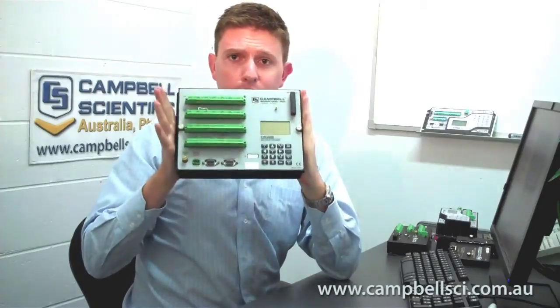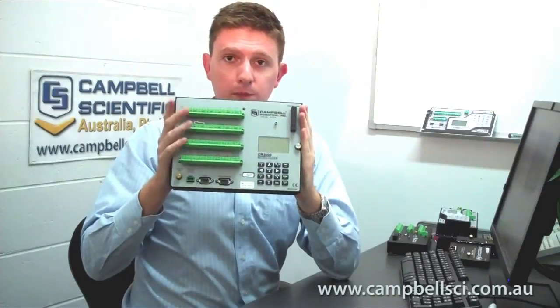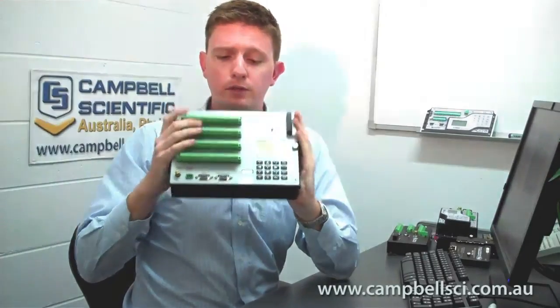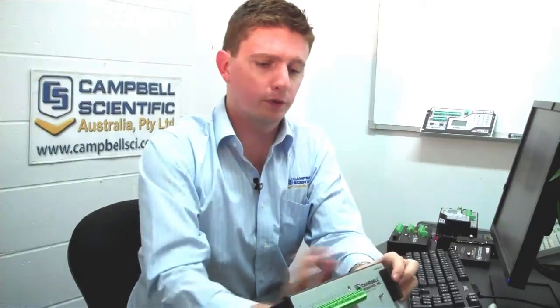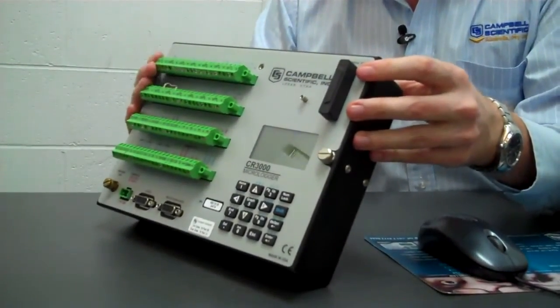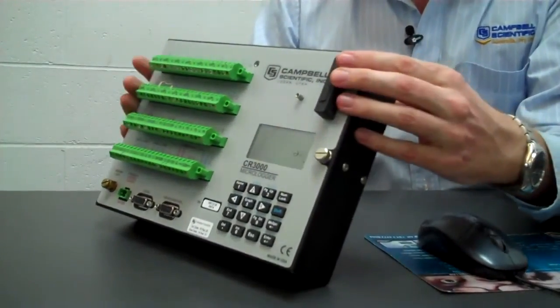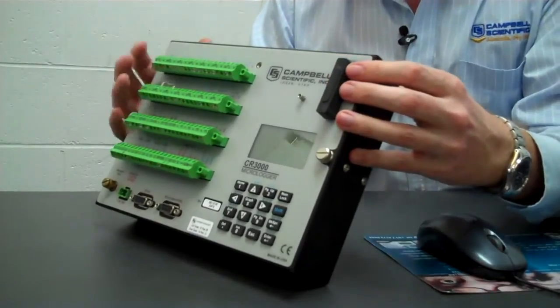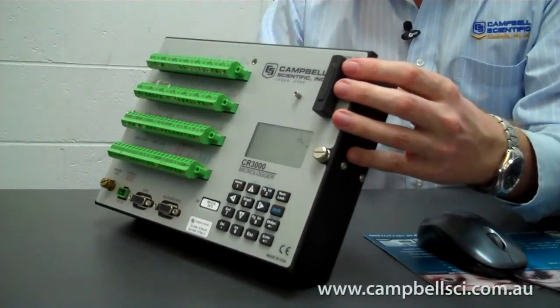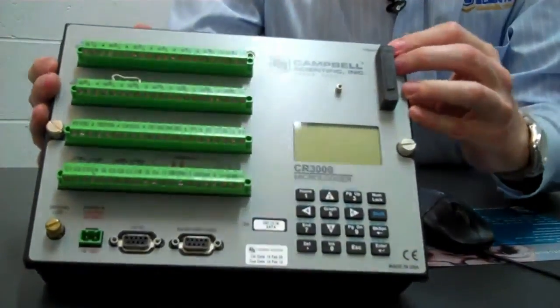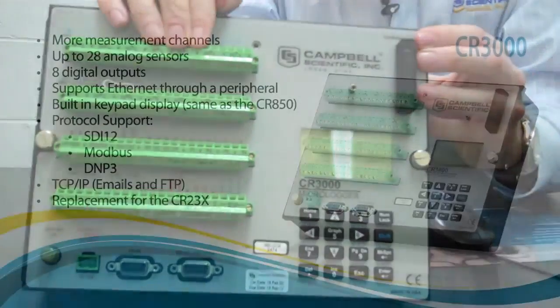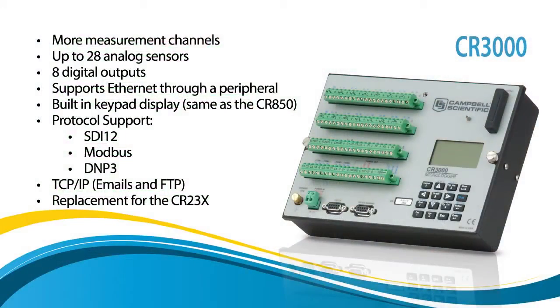The last one on our list is that big one there — the CR-3000. It's the big boy of the group and fits above the CR-1000 in our scheme of loggers. It has a lot more measurement channels — 28, as opposed to 16 for the CR-1000 — plus 8 digital outputs, a keypad display, and a peripheral port. It has the same RS-232 and CSIO ports, same programming language and instructions, and it can do emails, FTPs, and SMS — all the same things the CR-1000 and CR-800 can do. But it has a faster processor, so it can do more processing in the same amount of time.